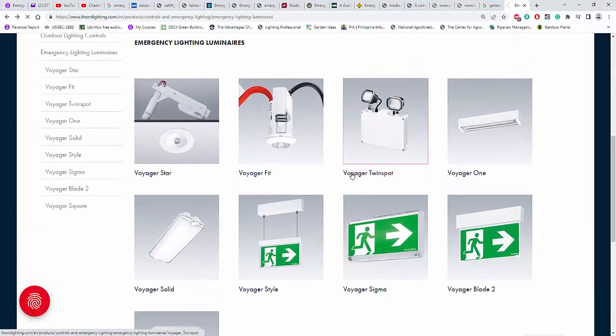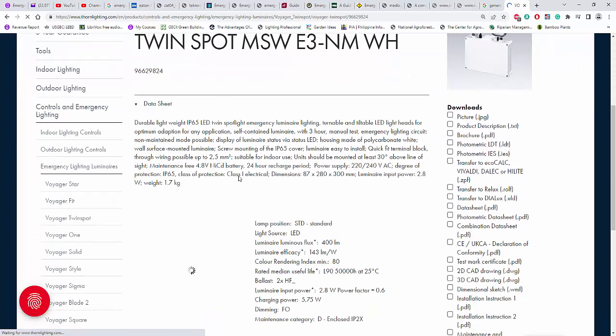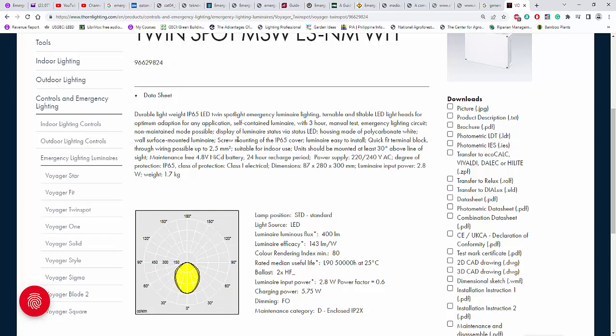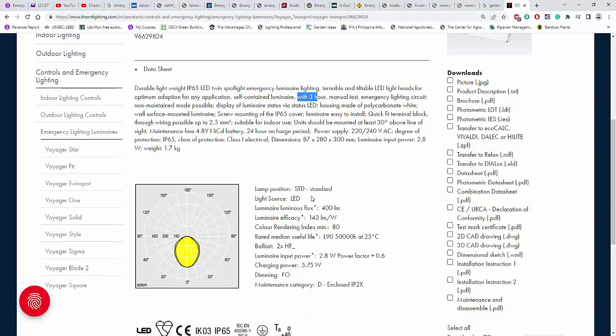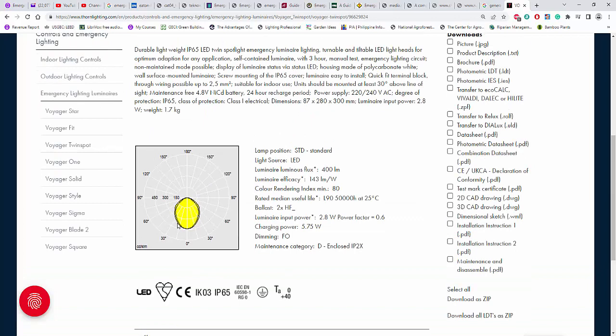For this Voyager Twin Spot, you can see the code E3 — it means it is three hours non-maintained. NM means non-maintained. So it's durable IP65, and you can see the words 'non-maintained mode possible.' It has three hours with manual test and emergency. It's self-contained with non-maintained and three hours. You can immediately see from the code: three, non-maintained. Look at the photometric diagram here — it's a little similar to a downlight, a little floodlight, and unlike the small one we previously saw, it's a little batwing type of photometric.